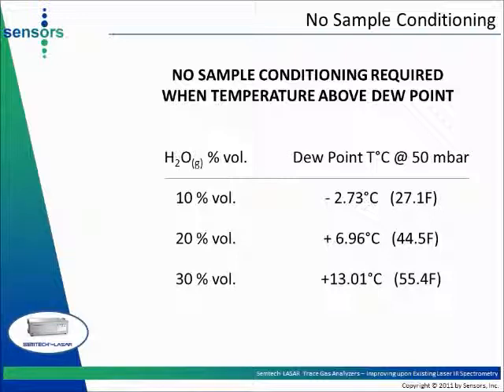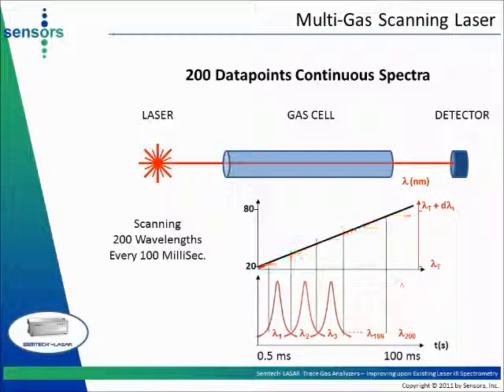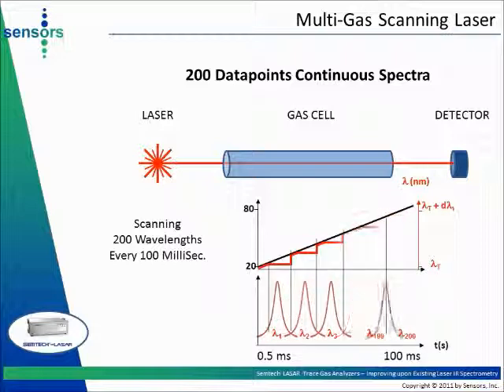If the operating temperature drops below the dew point temperature, only mild heating of the sample lines is required. The Semtech LASAR is a scanning laser spectrometer. Wavelength accuracy is controlled at 0.01 ppm by means of temperature control of the laser. Varying temperature to change laser wavelength is a slow process and may compromise wavelength accuracy. Instead, a current ramp is applied to the laser to change the emission wavelength, allowing very fast scanning of a large number of wavelengths — yielding 200 data point spectra every 100 milliseconds — without compromising wavelength accuracy or reproducibility.